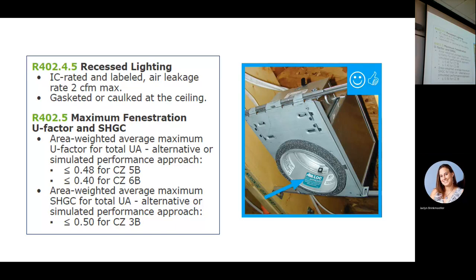So if you had 1 or 2 windows that were higher than 0.4, if you took all the windows and did an area weighted average, and it comes out at 0.4 or lower, then you can still put those in. And if you have a question on area weighted, send me an email, and I have a couple of slides that go through it. That basically is you account for how much area do you have at each U factor.